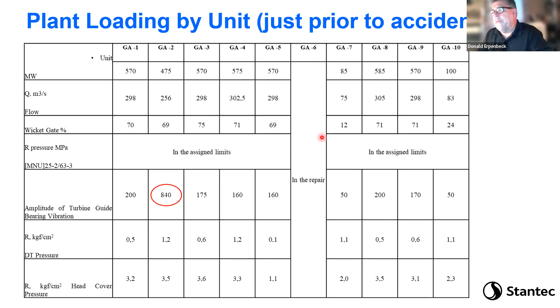Now, a couple of things. As with most critical accidents that occur, they don't happen because of just one thing. They happen because of multiple mistakes when you get to this level of catastrophic failure. First thing that happened was a fire in the control room at a nearby plant. And so the other plant was primarily doing the automatic generation control, which is basically responding to the frequency and holding the frequency at 50 hertz. They basically put the machine in auto and watch what's going on in the transmission grid. And if the frequency deviates at all, it starts to raise and lower the power automatically.